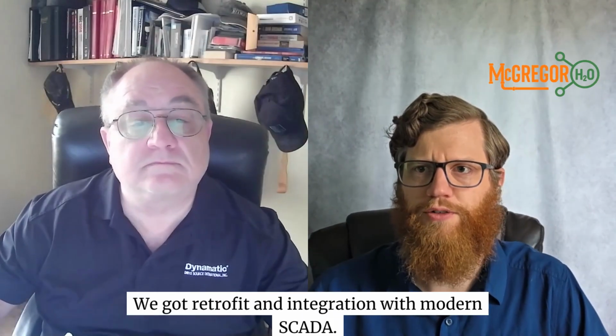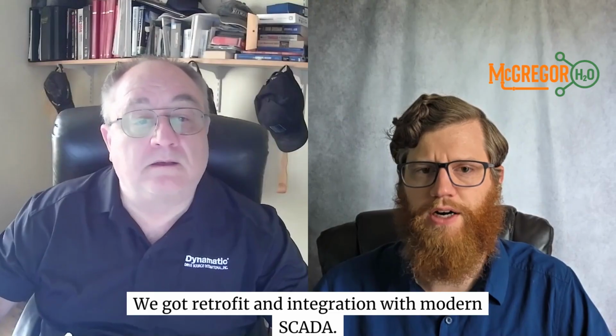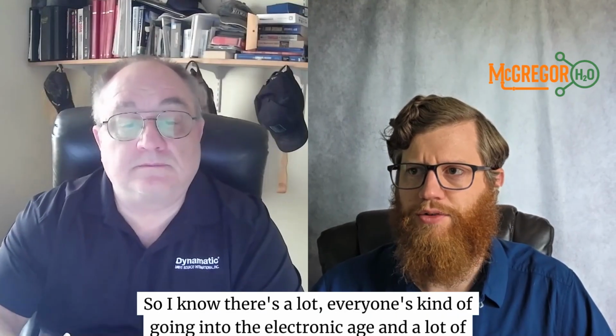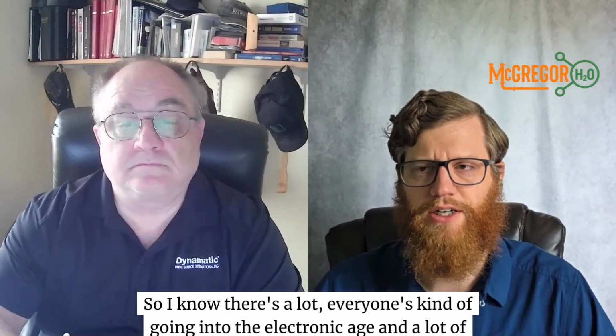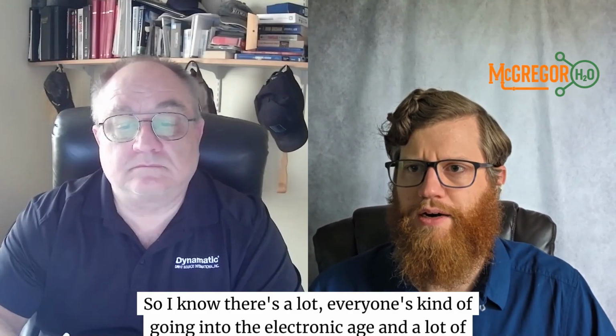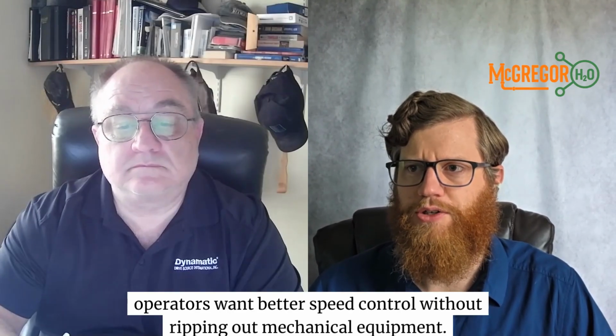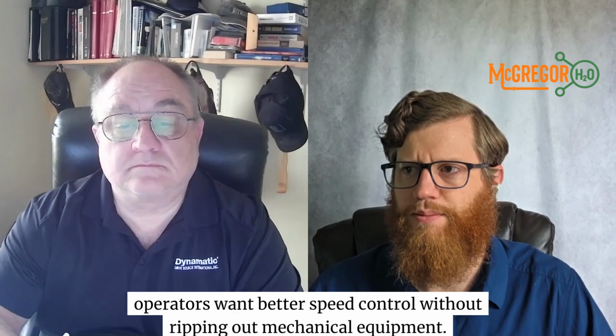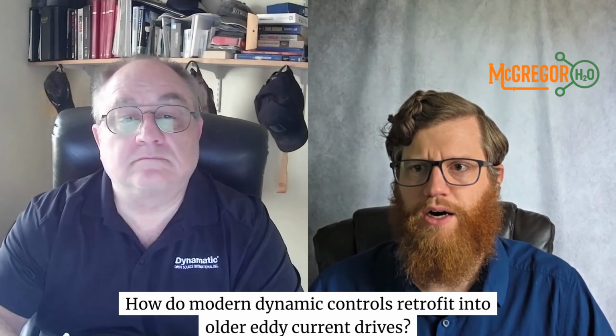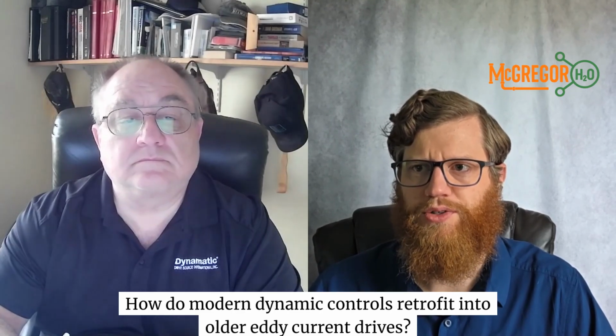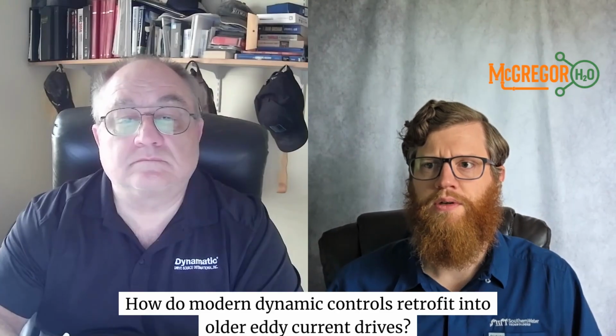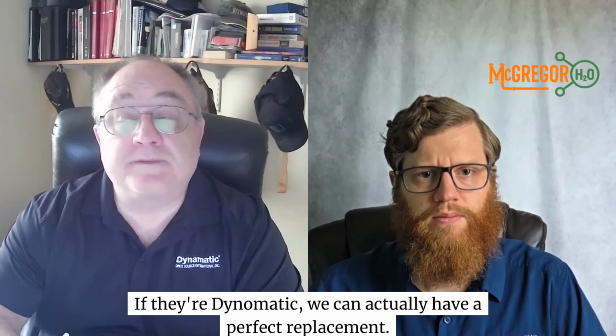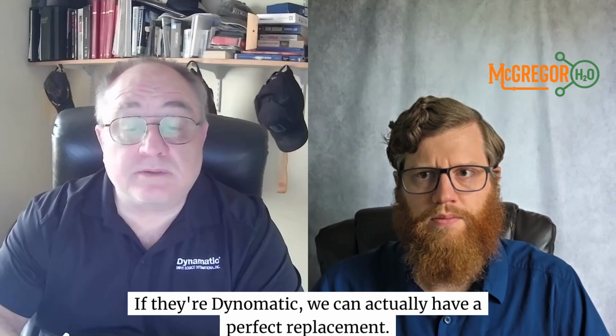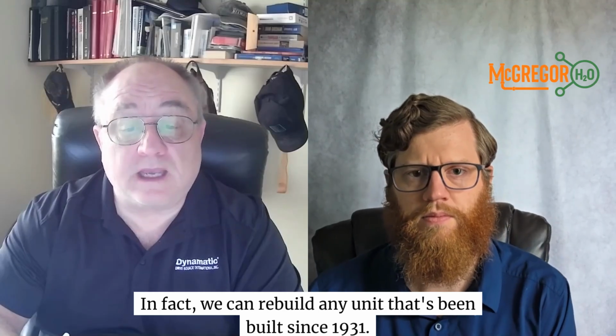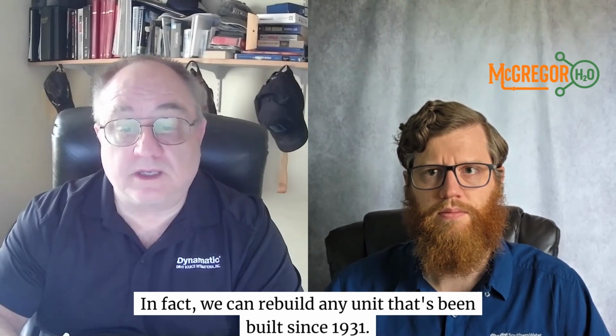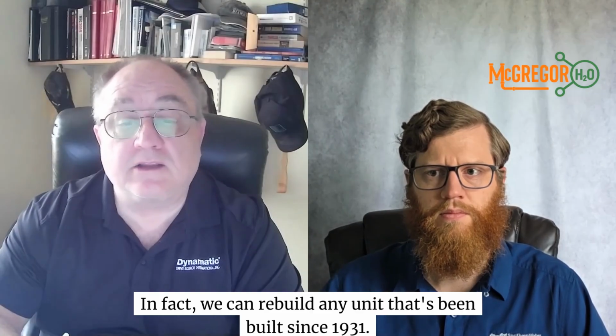We got retrofit and integration with modern SCADA. So I know everyone's kind of going into the electronic age, and a lot of operators want better speed control without ripping out mechanical equipment. How do modern Dynamatic controls retrofit into older eddy current drives? If they're Dynamatic, we can actually have a perfect replacement. In fact, we can rebuild any unit that's been built since 1931.